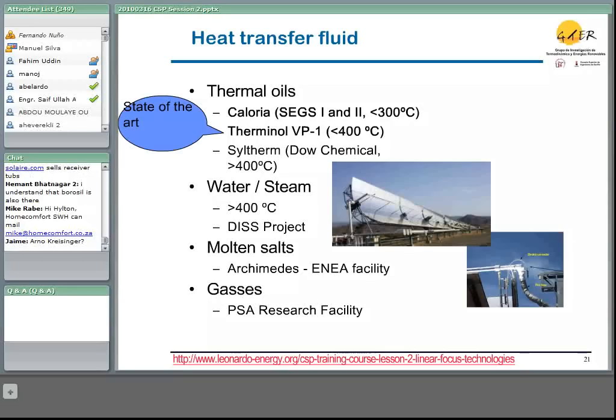This is a synthetic oil which can operate without degradation at temperatures up to 400 degrees C. So this is more or less the limit of operating temperature for these parabolic trough thermal power plants, with thermal oil as heat transfer fluid. This is currently the state of the art. Not only the nine SEGS plants, but also the plant that Acciona built near Las Vegas.